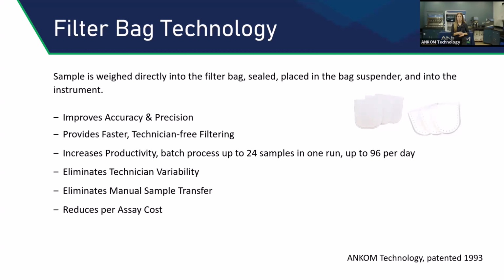This improves accuracy and precision greatly. It allows for larger surface area for the full filtration of the sample, as well as complete encapsulation and constant digestion. Because your sample is fully encapsulated, we can put it in the vessel under pressure and high temperatures, and the analysis is done much faster with technician-free filtration, and we can batch process these samples. I mentioned we can do up to 24 samples in one run, compared to the other options out there, which I believe are generally around 6 samples per run.